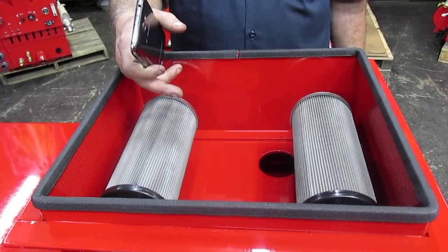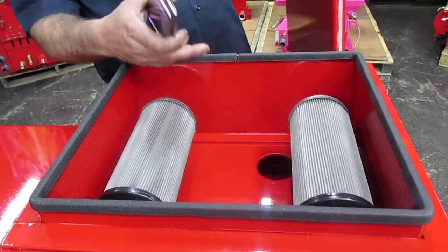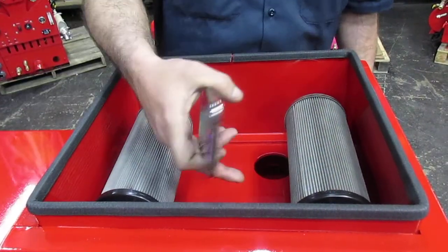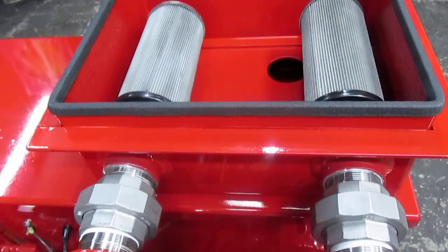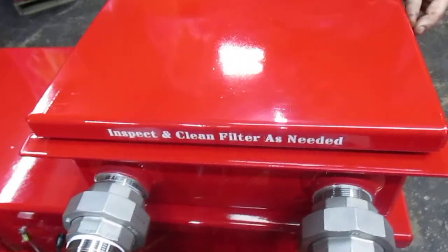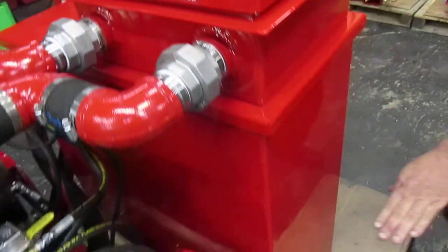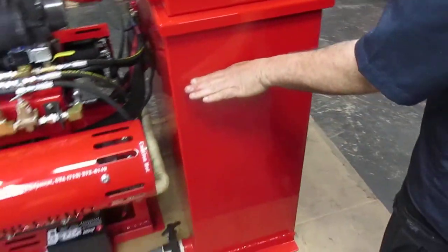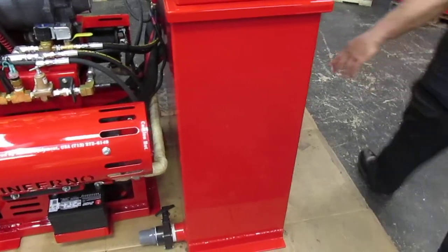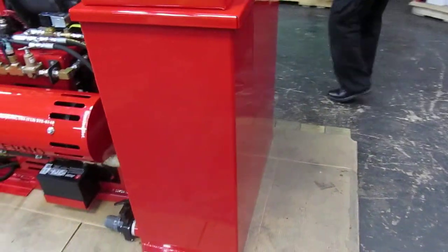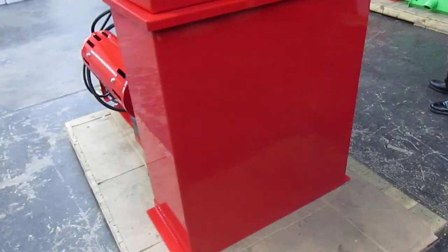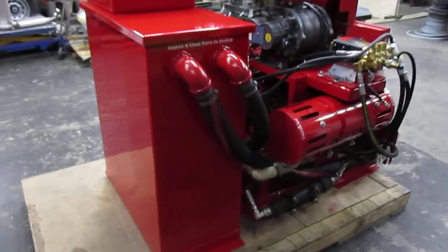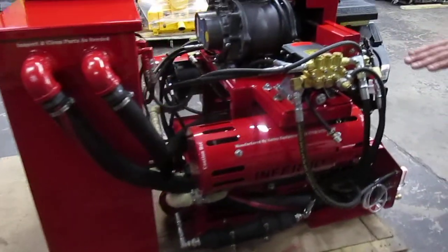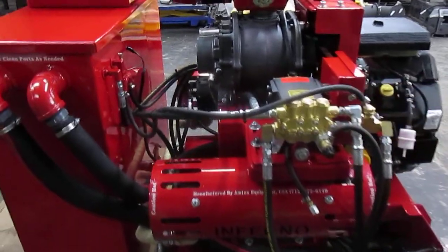That means the unit can go a good 100 hours before cleaning those filters, because we're separating the area where the air moves versus where the recovered water enters. At the same time, by having a top filtration housing or exterior filtration housing, you're allowing the tank to get about 90% of her capacity filled with gray water before shutdown. Now as we come around, some of the other changes that we have done to this design: by repositioning the heat exchangers in a lower panel, it allows us to design the pump to be right next to the blower, much more accessible as far as services, repairs, and what have you.